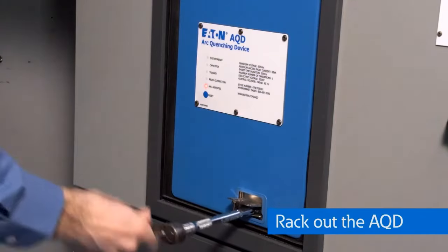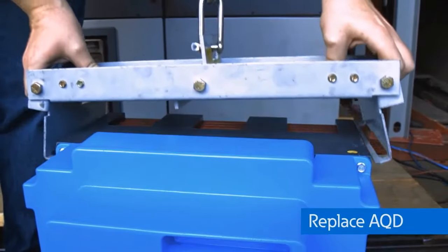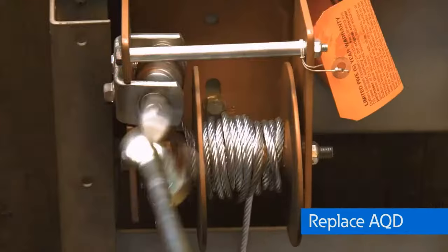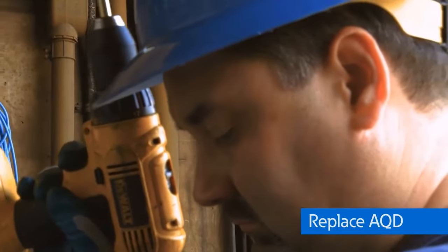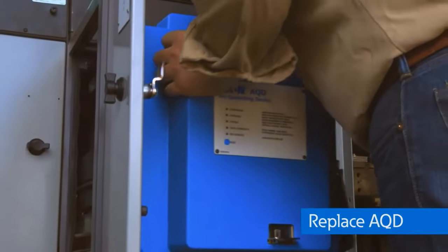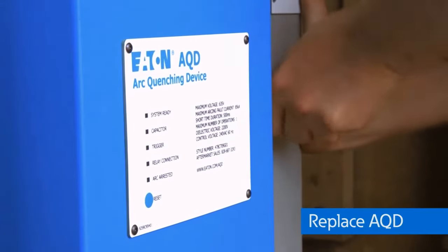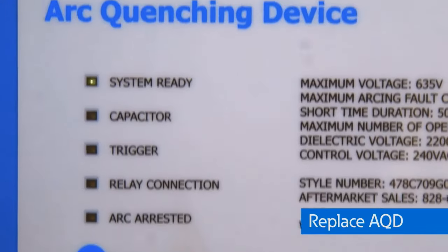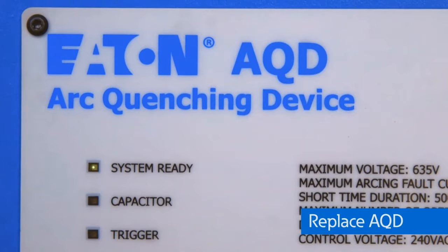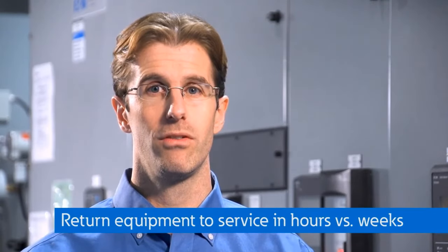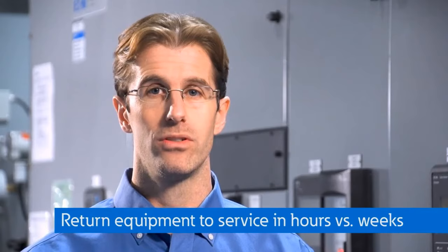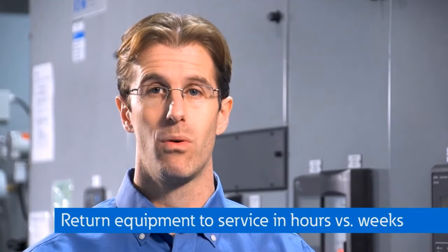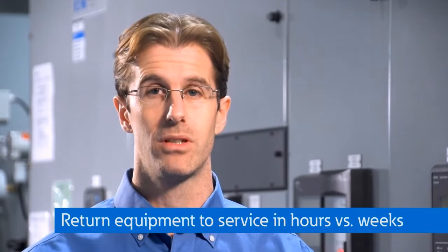It's a one-time use device, sort of like an airbag, and you'll replace it with a new one. If you don't have a new one on the shelf, that's okay. Once you clear the fault, you can still re-energize the lineup, but you won't get that 4 millisecond arc quenching time. And once you get a replacement arc quenching device, you can actually rack it onto the energized bus and be back up and fully protected. So with your skilled workforce, or with Eaton's engineering services on site, you can potentially have a lineup of switchgear recovered from an arc flash event in a matter of hours, instead of weeks or months, which may be required to repair or replace a heavily damaged lineup.